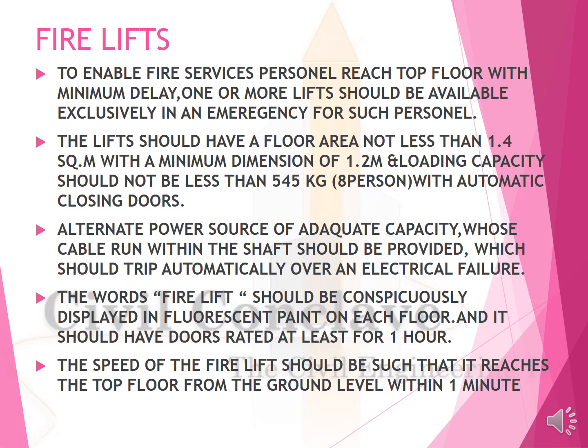An alternative power source of adequate capacity, whose cable runs within the shaft, should be provided, which should automatically take over in case of electrical failure. The words fire lift should be displayed in fluorescent paint on the fire lift on each and every floor, for which the door should have a fire rating of 1 hour. The speed of the fire lift should be such that it reaches the top within 1 minute.